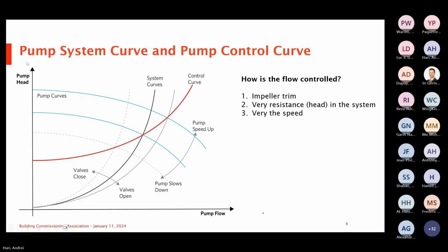Now, historically, if you had a pump operating at constant speed, constant volume, you are running on the blue lines. And as a valve chokes off, you move up on that blue line, and that is your new flow. But the reason you have that adjusted flow is because you're controlling on pressure or head, changing the resistance. The other way you can adjust flow is with the impeller trim. When you go to variable speed, you are running on what is referred to as the control curve.